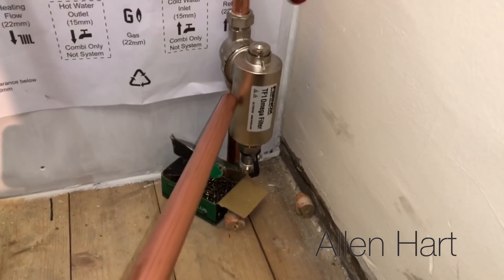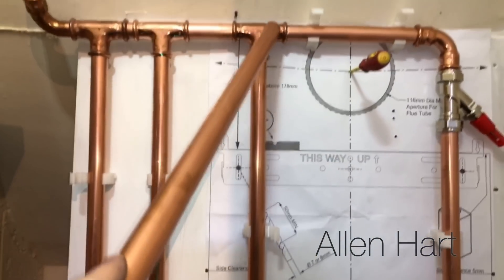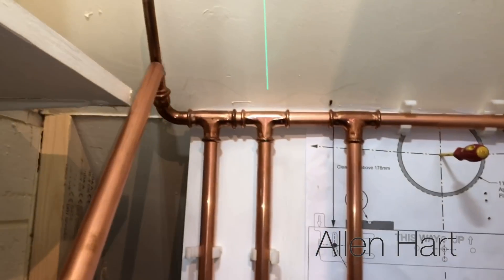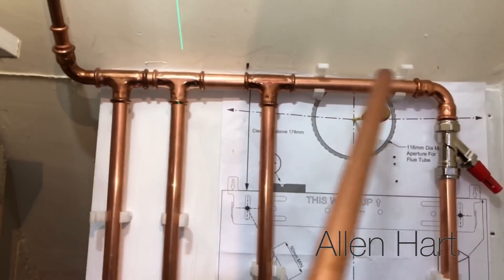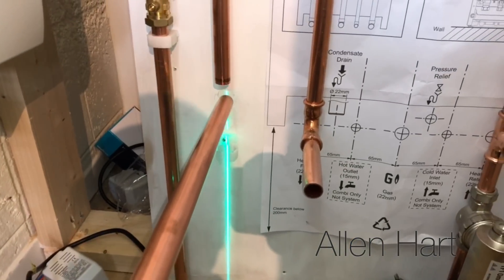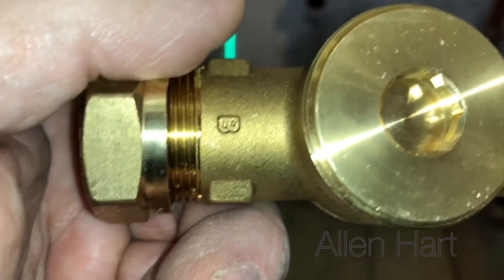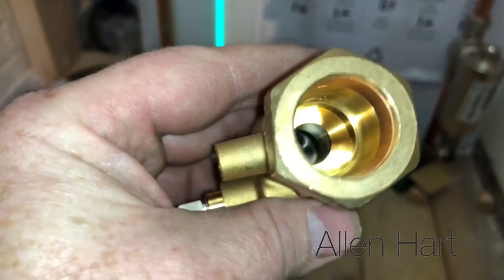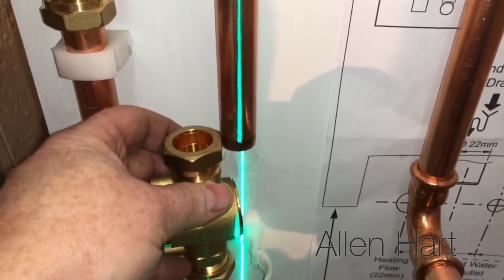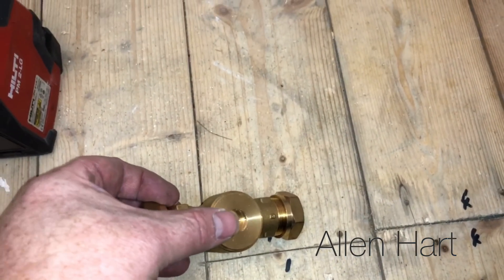We've got a Omega filter on there - that's the return back into the boiler. From the top, going around the flow, we've got two zones and then a manual air vent up there just so we can bleed that section of pipework. I've got one zone valve there and I'm going to put another zone valve here. Just to show you - on a zone valve there's an A and a B, so the zone valve only goes one way. On this one the flow comes down from the flow in that direction, so when you look at the valve, the flow would go that way.